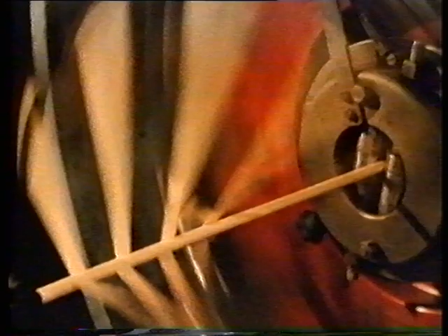Next, the conductors are insulated using a paper lapping process. A semi-conducting shield of 2 carbon papers is first applied immediately over the copper conductors. Machine heads then wind layers of wood pulp paper onto each conductor to make it precisely 2.8 millimeters thick. Finally, a numbered tape is added for core identification, followed by a perforated metal foil laminate to form the core screen.